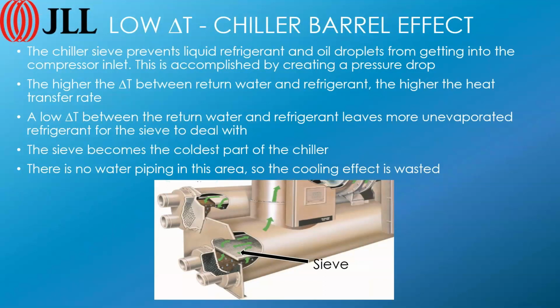So if you have a low delta T with a lot of liquid refrigerant left over, as that refrigerant is being sucked up into the compressor inlet, it hits the sieve and it flashes off. And with a system that's a low delta T, that sieve, again not in contact with the water in any way, will become the coldest piece of metal in the entire system by far. And it will actually become the world's biggest wind instrument. Low delta T chillers are very noisy because of exactly what you're seeing there. So it's just wasted energy. Low delta T just wastes energy at the chiller. Reduces its capacity and things of that nature as well.